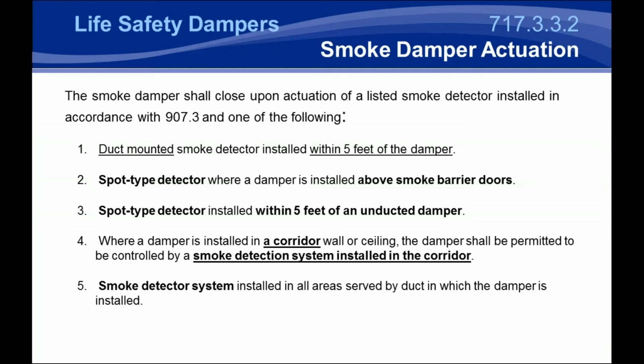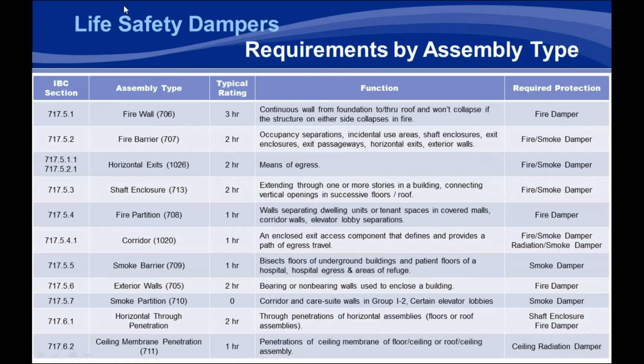Now, for tenant improvement, a lot of times it's worth having that smoke detector with the damper shipped loose, because a lot of times it's not clear as to what is existing in the building. For these tenant improvement type renovations, what you'll find is a fire barrier has now become a fire smoke barrier with that added requirement of leakage protection. Because of that, you want your damper to close in the presence of smoke, so you may need to have that smoke detector mounted.